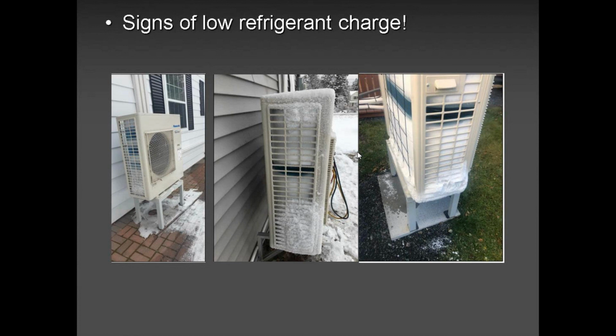So it's very hard to believe that the system came with low refrigerant. What I have noticed is guys are using a lot of nitrogen. And when they use a lot of nitrogen, they push past those service valves, the rubber seals. And that's where the R410A tends to escape. So please don't overpressurize the system. 400 or less is more than enough.